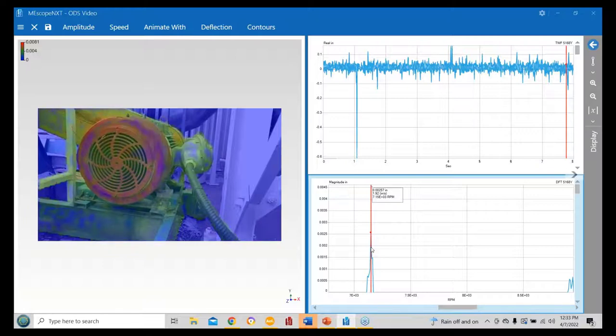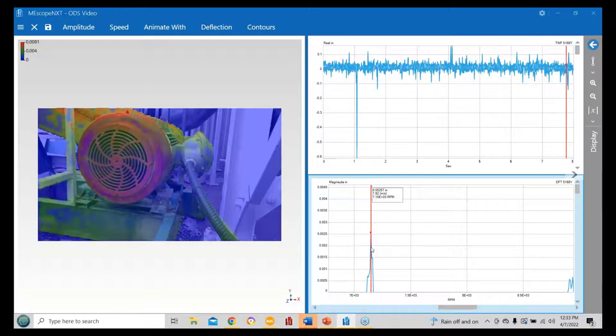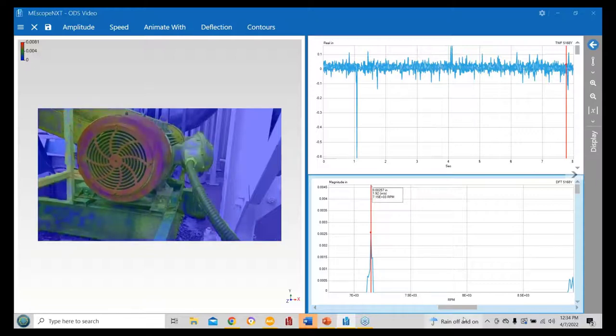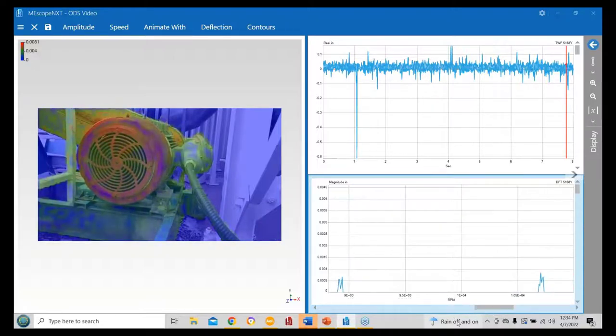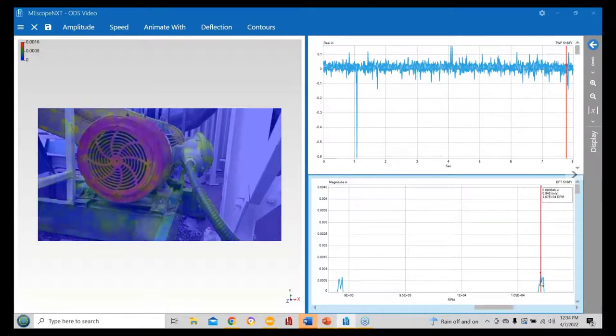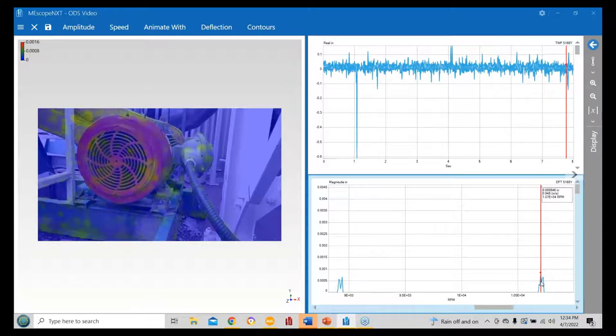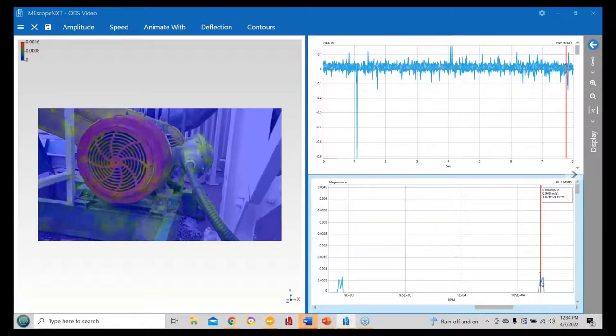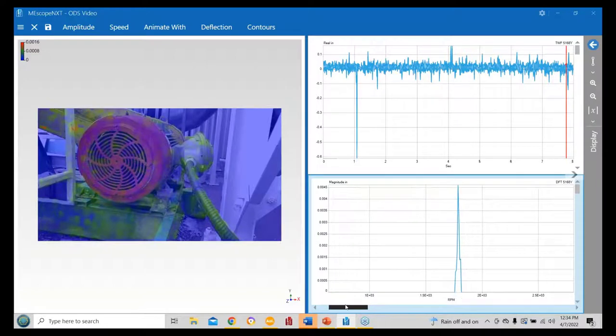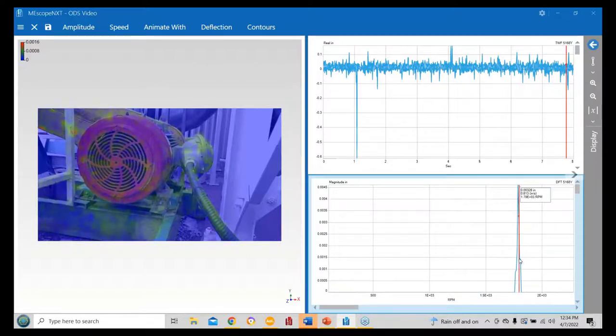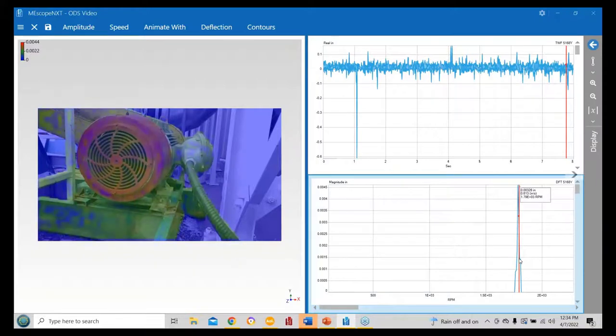At the bottom you can see the unfolded frequency range. I can select each band and see the operating shapes. At 1,790 CPM turning speed I get 0.363 inches per second and can see the machine bouncing up and down. I can step through two times, three times, four times running speed and see the frame motion. At four times there's a lot of vertical bouncing motion and a little off-axis twist. It's a good machine to learn with because it really shows a lot of different fault indicators.